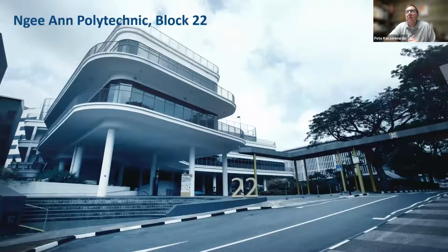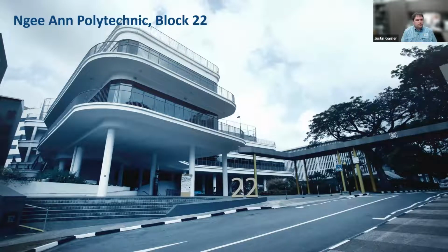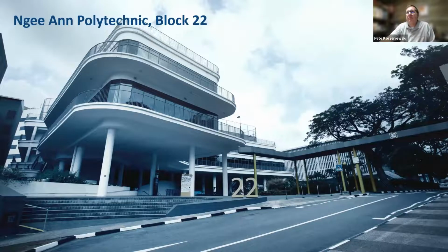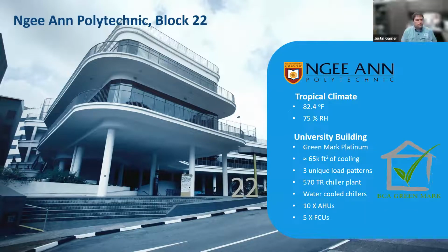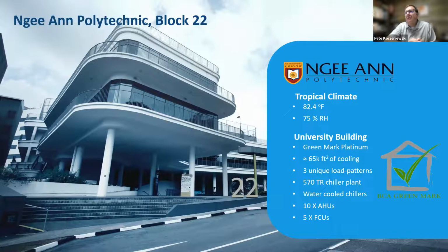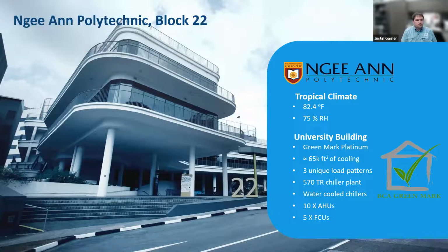To take a look at the inspiration for this, we were working with an engineering school, Ngee Ann Polytechnic in Singapore, and in particular, this Block 22 building that you're looking at. It's a mid-sized, 85-acre campus, and this was a relatively new building for the engineering school. It had some lab space and some other facilities for the campus, sort of a mixed-use building. Singapore has a very tropical climate, similar to southern parts of the US. It was built not too long ago, as a Green Mark Platinum building, which in Singapore, as far as I've been able to research, is a pretty close equivalent to LEED. There were a lot of different load patterns in the building, 570 tons of chilled water, and a combination of 10 air handling units and 5 fan coil units.